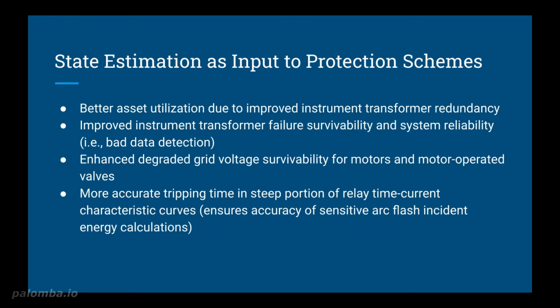But first, let's talk about some applications that could significantly be improved by using state estimation as input. For example, let's first look at motor protection. Thermal overload relays are often used in industrial settings to protect motors from overload conditions. These are typically bimetallic contact devices that separate upon heating due to increased current levels flowing through them.